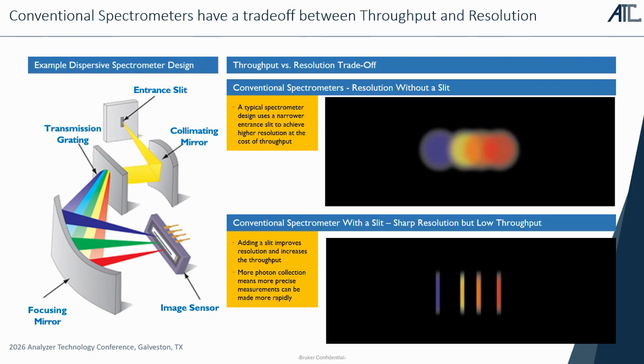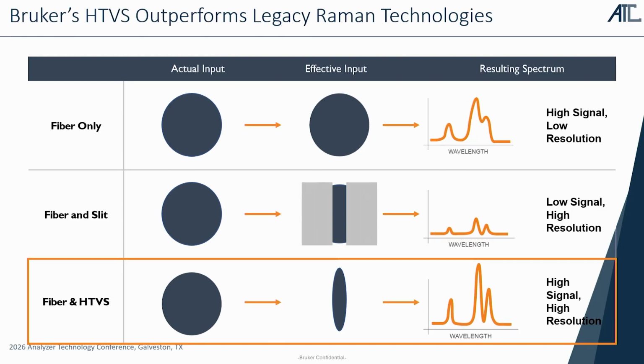So we talked a minute just about resolution and things like that. What does that mean, right? Essentially you get a bunch of light back, and you know that you're not getting a lot. You're only getting 1 in a million photons coming back up that pipe. So you've got to do as much with the photons that you have, right? And that's where this segmentation comes in. Conventional spectrometers just have what they call a mask slit. That is really just a piece of metal with a slit in it, and that allows only a very small amount of these photons through, right? And you can see what that does to resolution.